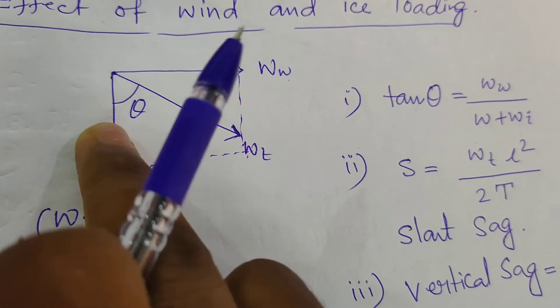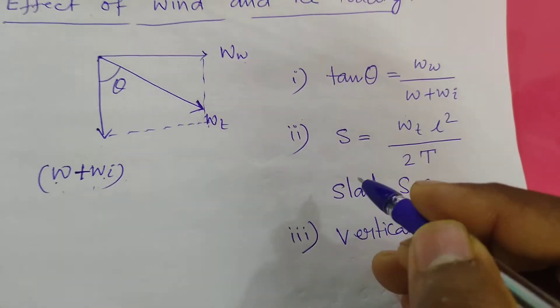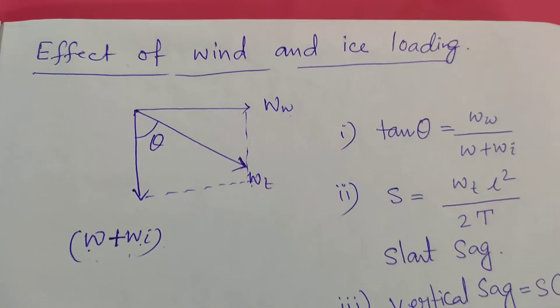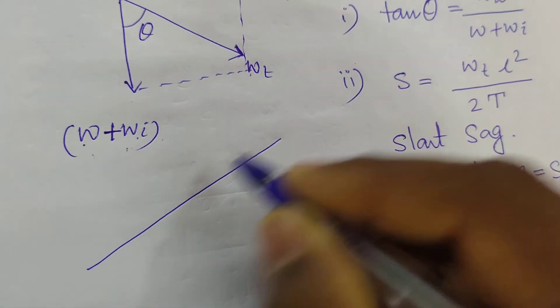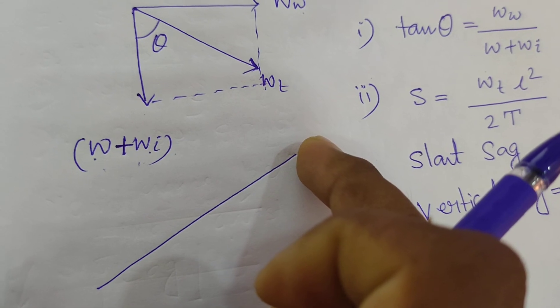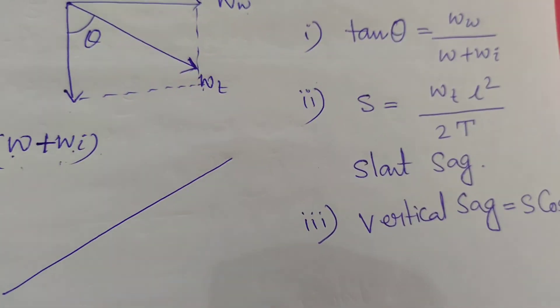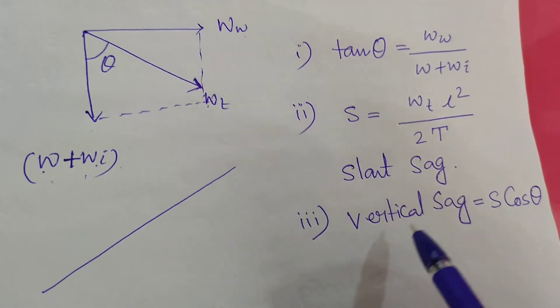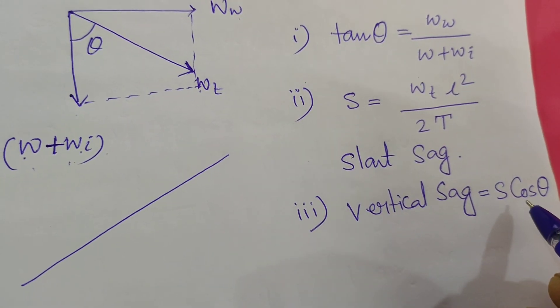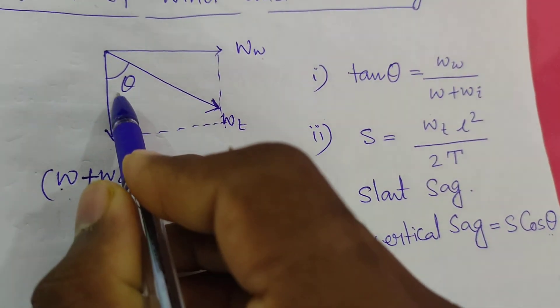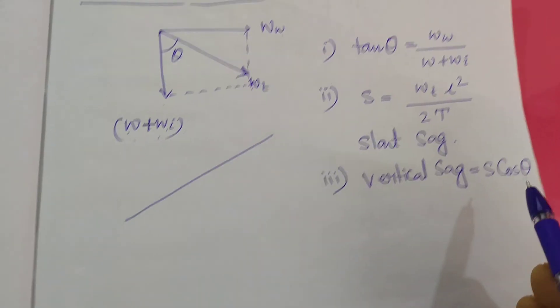The angle theta is given by: tan theta equal to WW by (W plus WI). This gives the slant SAG — the SAG along the inclined direction. Slanting means the line is inclined, not horizontal. We can calculate the slant SAG using this formula. For the vertical SAG, if we know the slant SAG and the angle theta, then vertical SAG is calculated by multiplying the slant SAG by cos theta.